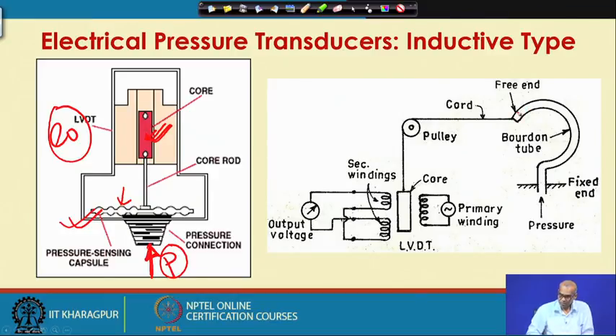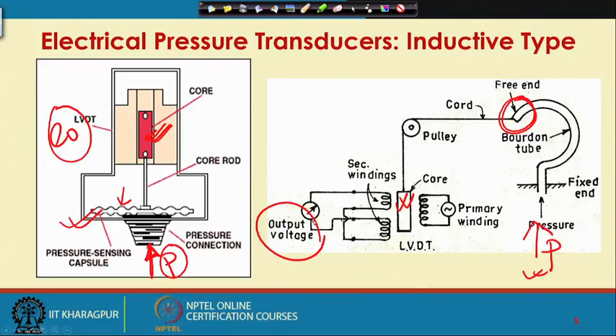Similarly, you have a Bourdon tube here. You apply pressure inside the Bourdon tube, the free end will show displacement. See, that displacement is used to move this LVDT core. So, in this, when you apply pressure inside the Bourdon tube, this shows displacement. Accordingly, the core of the LVDT goes up or comes down depending on the magnitude of the pressure, and depending on that you will get an output voltage. So, this output voltage is related to this pressure.